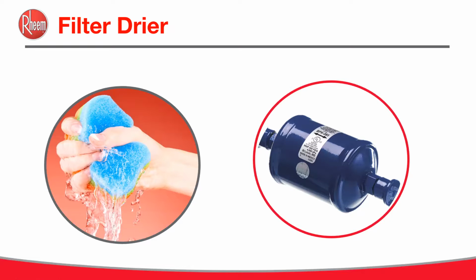It is also good practice when replacing a filter dryer to cut out the old one versus unsweating it. Why? If you unsweat it, it's going to possibly release moisture and contaminants back into the system. I know we're all using nitrogen, but it's still better to cut it out versus unsweating it.